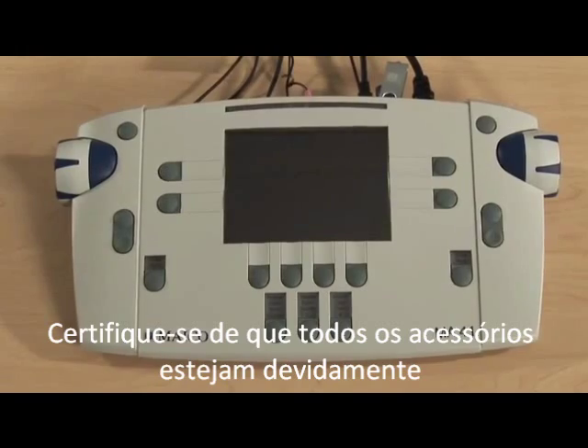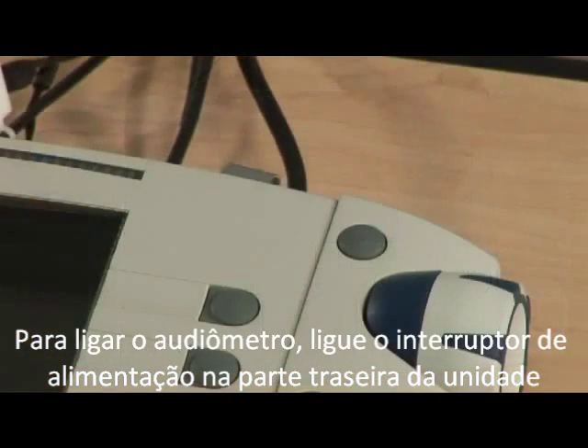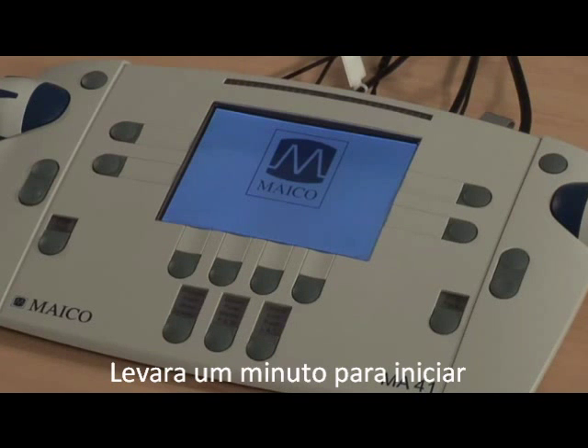Make sure all of the accessories are properly plugged into the audiometer. To turn on the audiometer, flip the power switch on the back of the unit. You will see the screen display light up and then the Maico logo appear. It will take a minute to boot up.